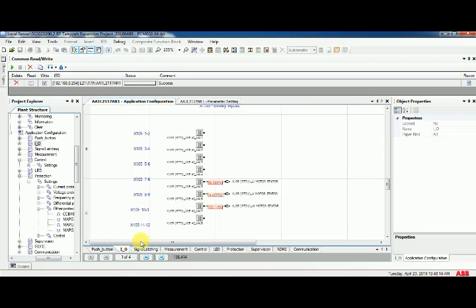Now you can see the value of RTD on U-phase also. As I said, input 5 is for RTD3. By seeing this, it can be clearly understood. And also due to different resistor values, the showing temperature is different.